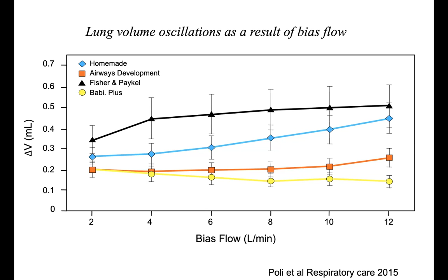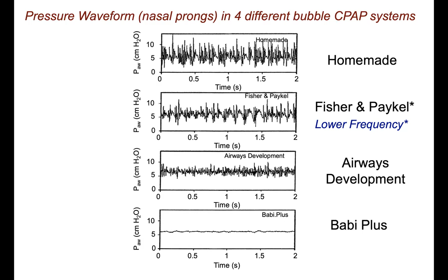And here's what it looks like if you actually measure the respiratory waveforms. Here again is the homemade device. You can see that the oscillations are quite significant. Here's the Fisher-Paykel device, which has the same oscillations, but at a slightly lower frequency. But the two others, Airways Development and Babi Plus, have markedly attenuated oscillations because they have this diffuser at the end of the expiratory limb.